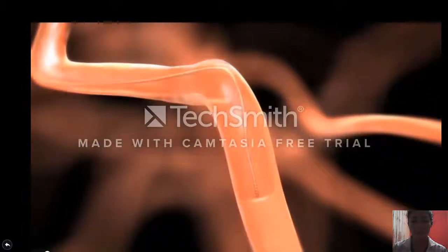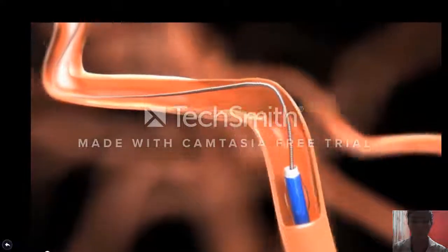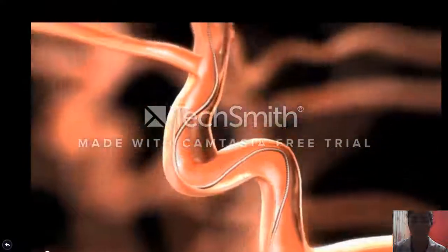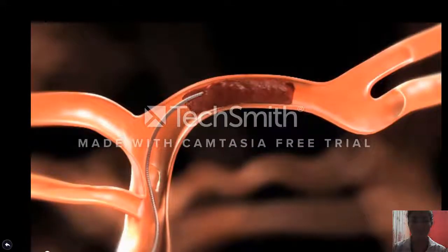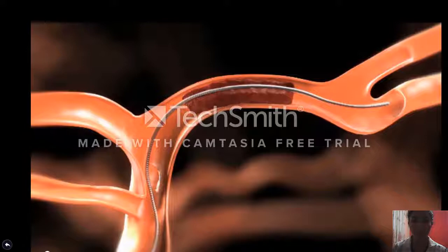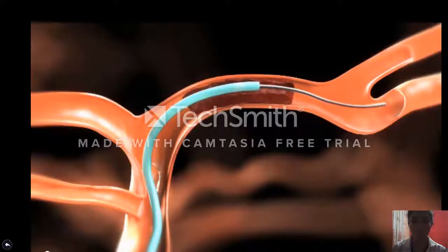Position the balloon guide catheter as close to the thrombus site as possible. Connect a rotating hemostatic valve, or RHV, to the fitting of the guide catheter, and then connect the continuous flush. With the aid of a suitable guide wire, hold the guide wire in place and advance the microcatheter. Position the microcatheter distal to the thrombus so that the usable length portion of the Solitaire FR will extend past each side of the thrombus when fully deployed.